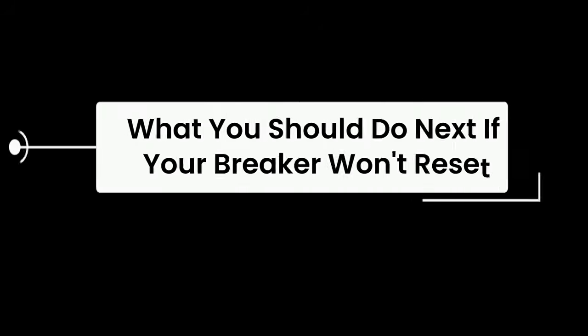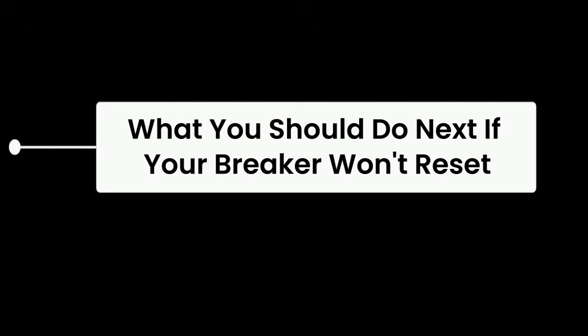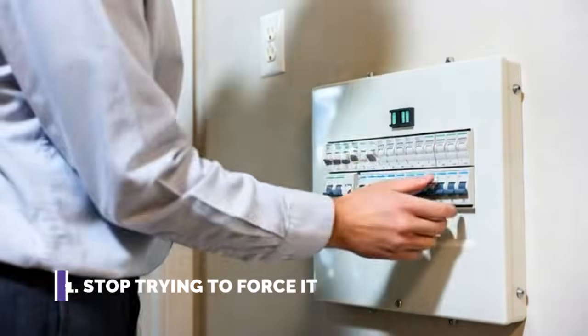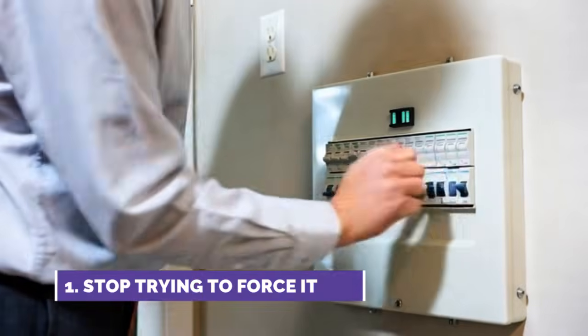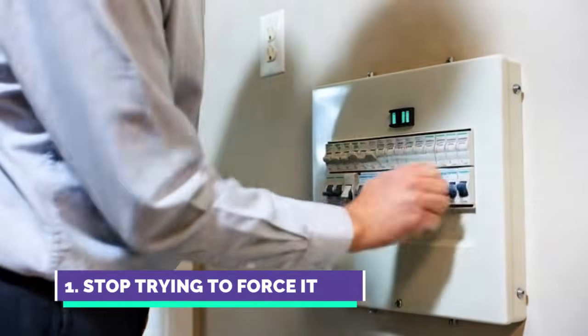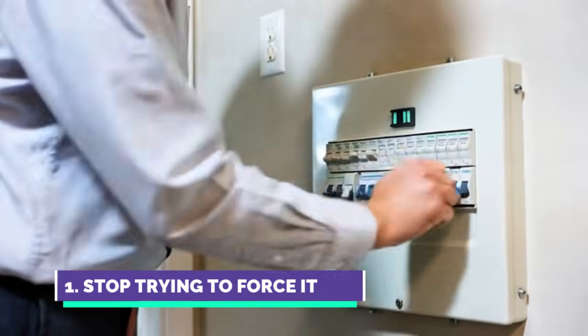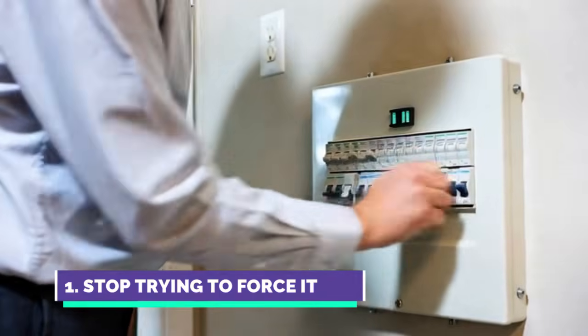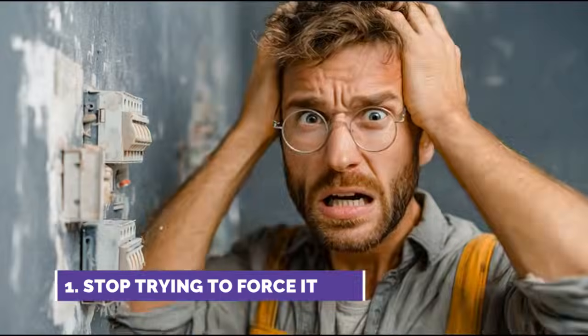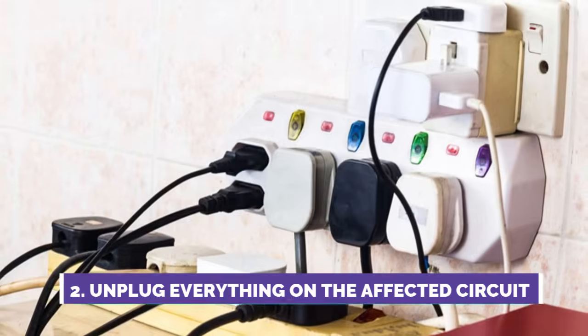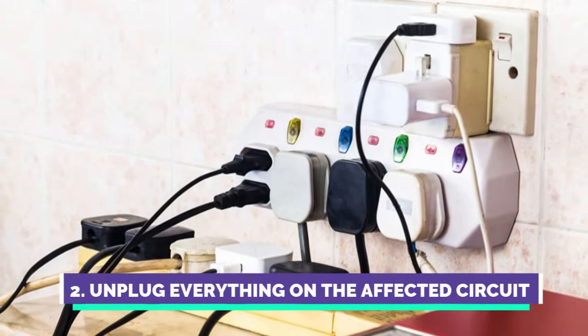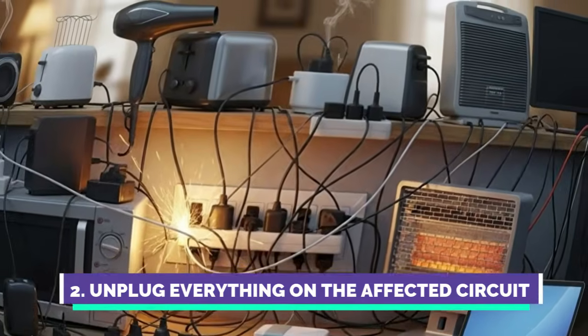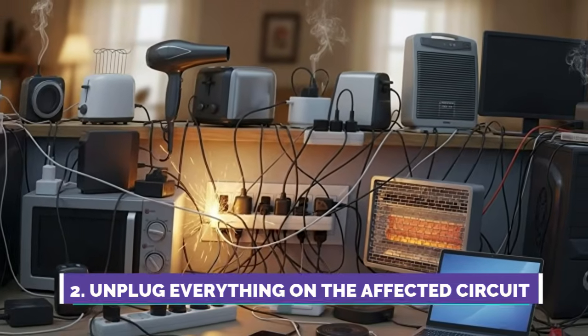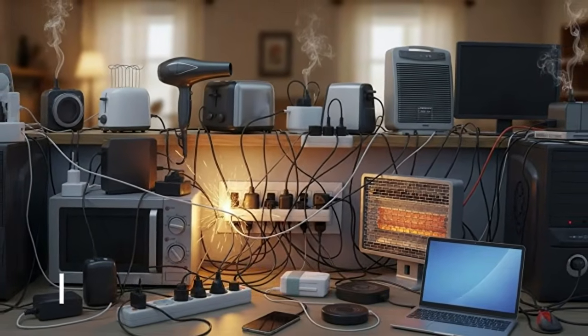If your breaker won't reset, here's your action plan. First, stop trying to force it. Every time you repeatedly flip that breaker, you risk damaging the breaker mechanism, creating additional arcing or worsening whatever fault exists on the circuit. If it won't reset after 1 or 2 attempts, leave it alone. Second, unplug everything on the affected circuit. Go around your home and disconnect every device, appliance, and lamp on that circuit. If you're not sure what's on the circuit, unplug everything in the general area.